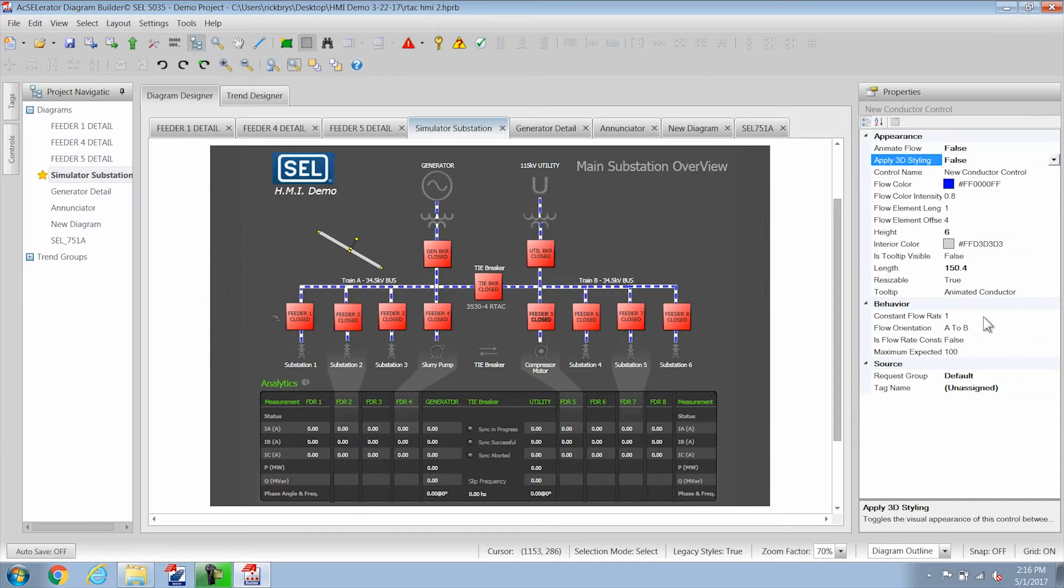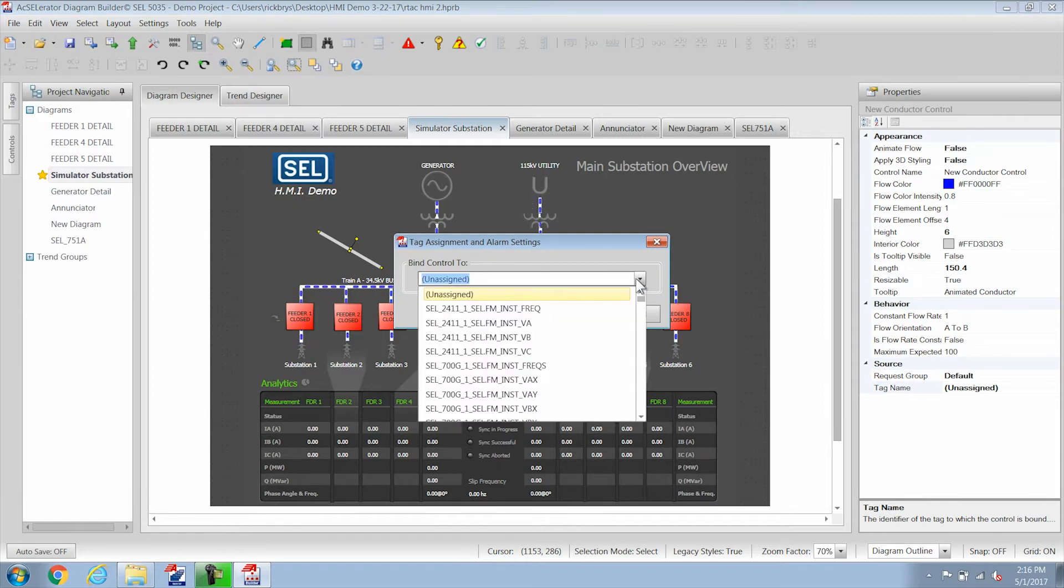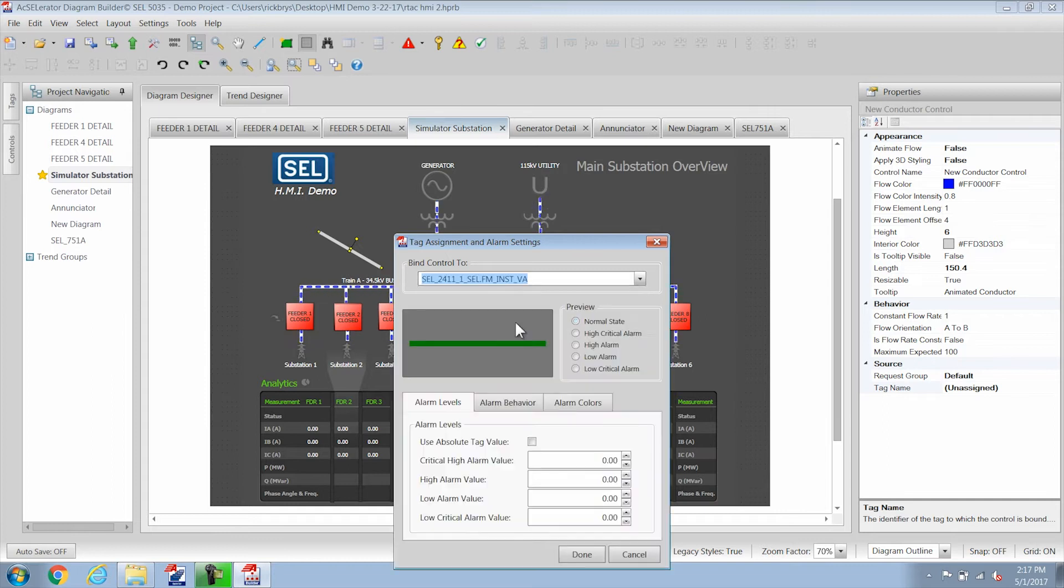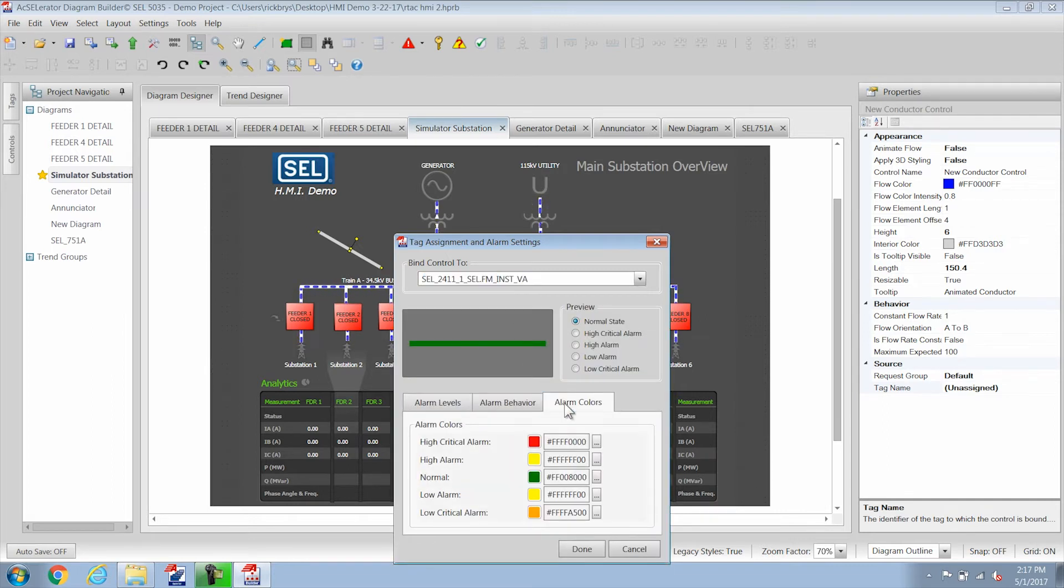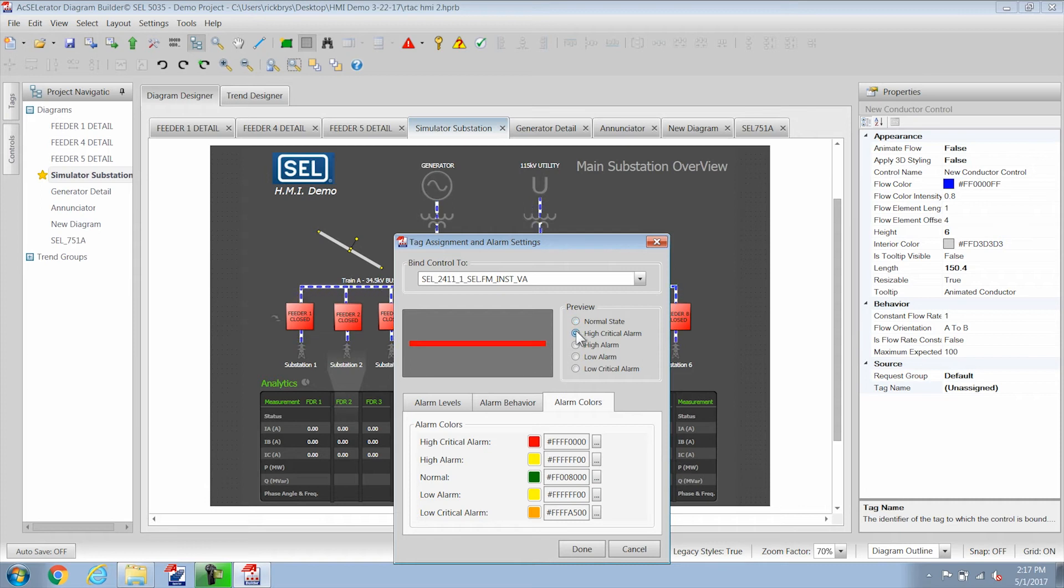And then while you're in here you can click on the tag name and assign a tag to it and all of the tags that are analog type tags will show up here. So I'm going to select a voltage and you can change the color of the conductor and also what it looks like in different alarm states.